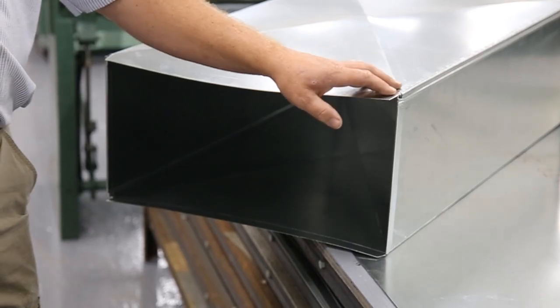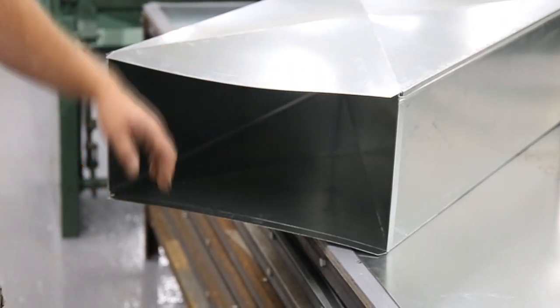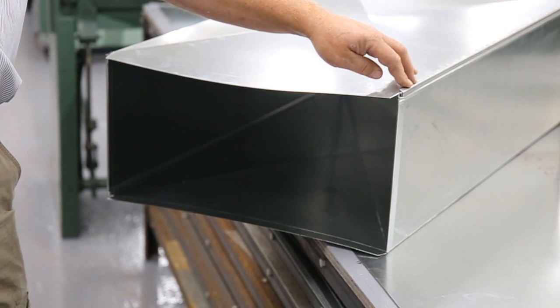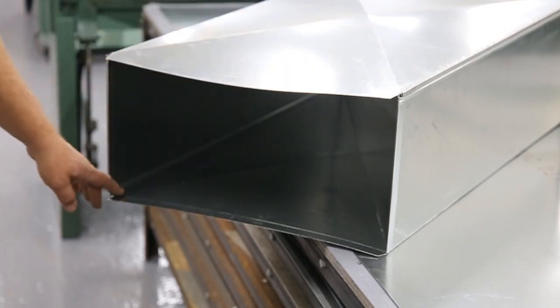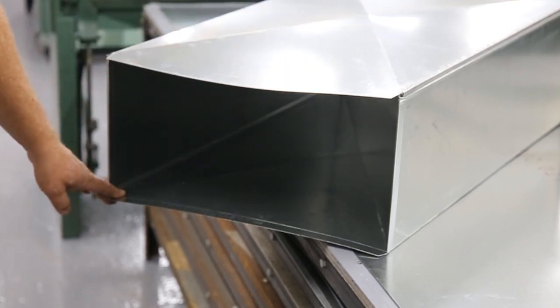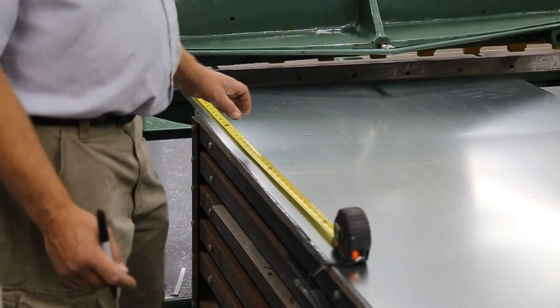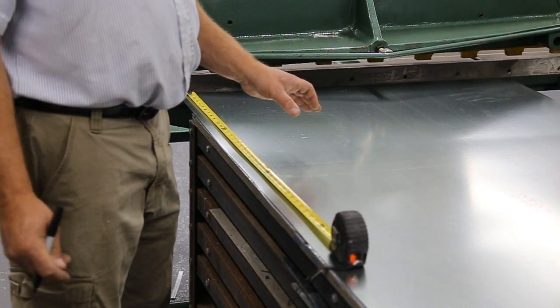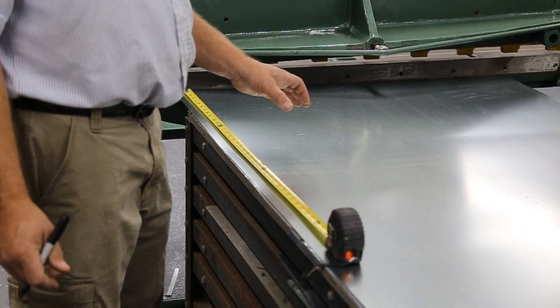We're going to make a piece of 20 by 10 duct. We have to allow 1 inch for the Pittsburgh seam, 1/4 inch for the male that fits into the Pittsburgh seam. To build a 20 by 10 piece of duct, we need the piece 31 1/4.